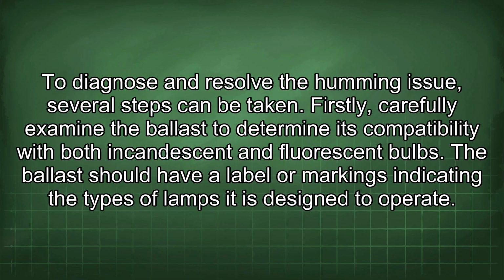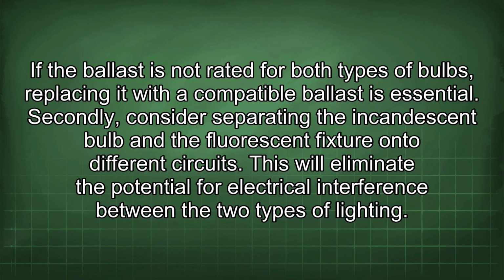Firstly, carefully examine the ballast to determine its compatibility with both incandescent and fluorescent bulbs. The ballast should have a label or markings indicating the types of lamps it is designed to operate. If the ballast is not rated for both types of bulbs, replacing it with a compatible ballast is essential.